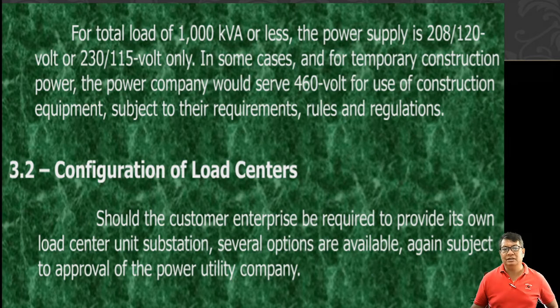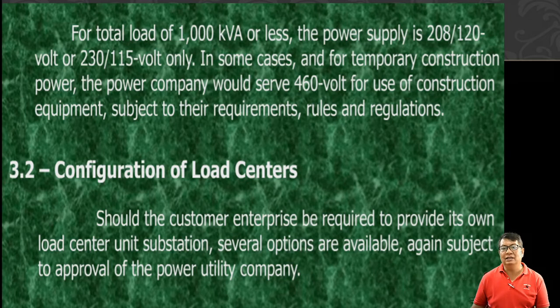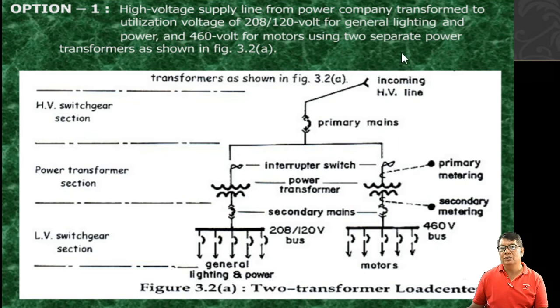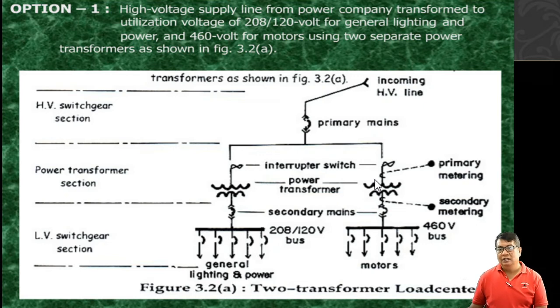For configuration of load centers: should the customer enterprise be required to provide its own load center unit substation, several options are available, subject to approval of the power utility company. Option 1: high voltage supply line from the power company is transformed to utilization voltage of 208/120 volts for general lighting and power, and 460 volts for motors, using two separate transformers as shown in the figure.